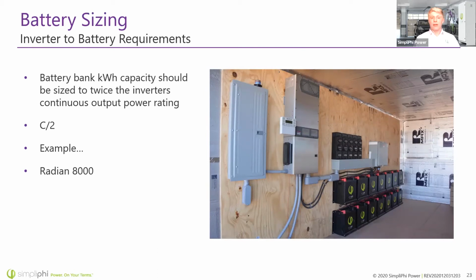The reason for that is our batteries can be charged and discharged fully at a rate of C/2, which means they can be charged and discharged in 2 hours. Now, if the Radian was pulling 8 kilowatts from a 16 kilowatt hour bank, it would take exactly 2 hours to discharge the bank. So you're sizing your bank properly to avoid any damage and make sure it's going to have a nice long lifespan and a good return on investment.